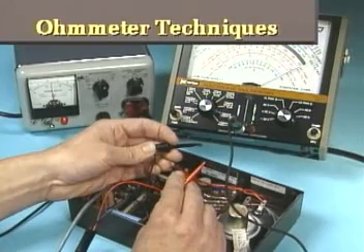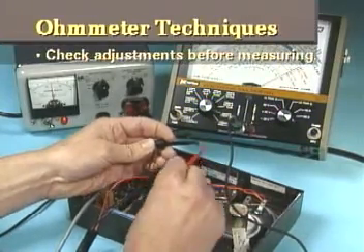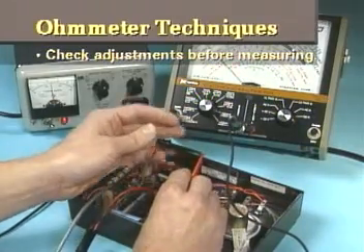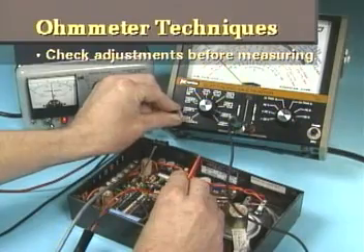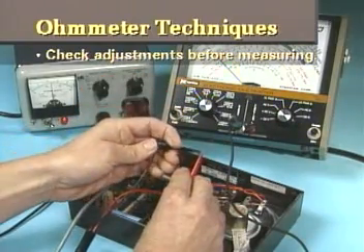Here's some techniques to be used for proper and accurate resistance measurements. The zero adjust and or ohms adjust setting should be checked each time an ohmmeter is used. The test leads are connected to each other and zero ohms should be indicated.